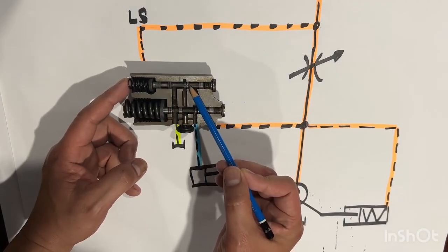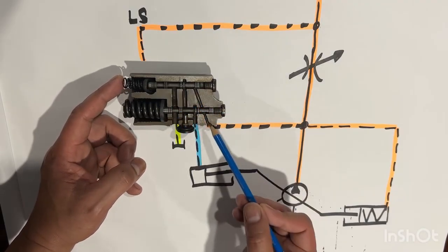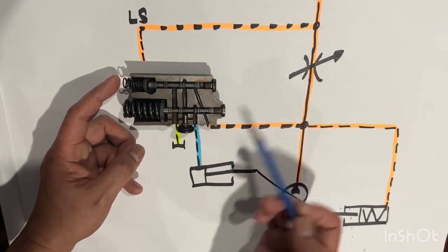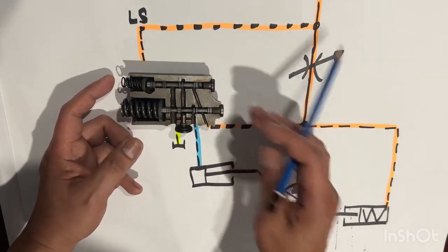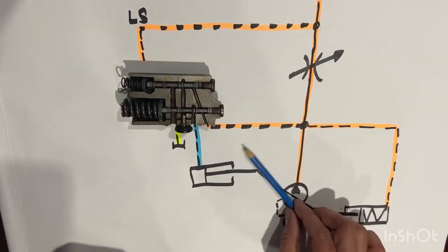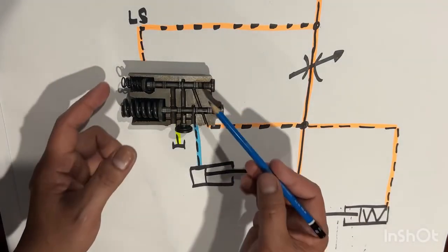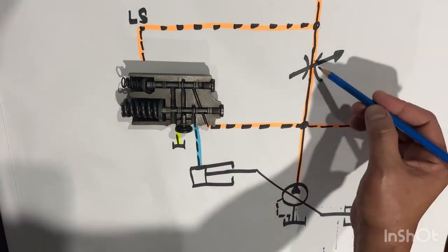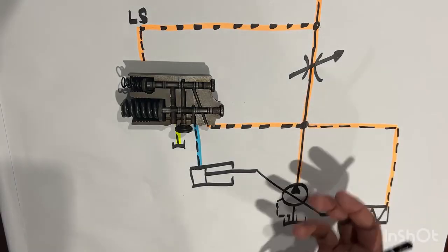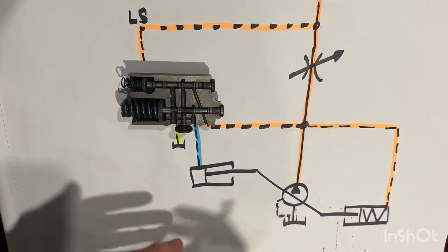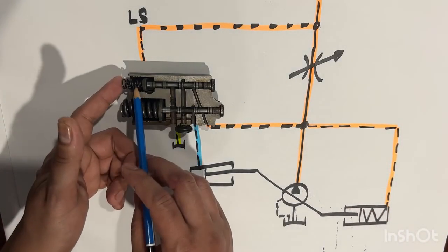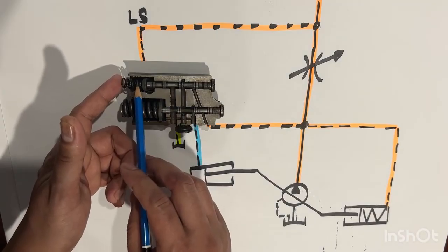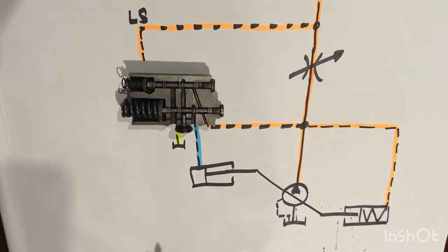spool here will shift to the left, and then allow the system pressure and this stroke port to be common or open. Once that happens, the pump will de-stroke enough to maintain the 16 bar standby pressure. So that is the standby mode. Alright, so when the control valve is closed, the condition of the system is standby, depending on how much setting you put in this spring chamber here in the upper spool. Okay?